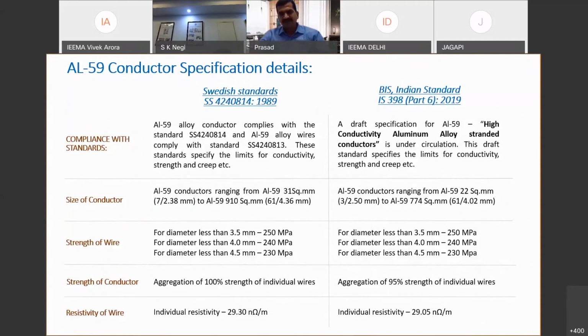But the important factor we can look at is how the overall UTS of the conductors is calculated. The Swedish standard allows 100% strength of the individual wires, which can be aggregated to arrive at the breaking load of the conductor, whereas in the Indian standard we have 95% of the individual strength of the wires. At the same time, in the Swedish specification, if we achieve 90% of the UTS which we have confirmed, then it is okay. Whereas the Indian standard is a refined version, and in the recent TBCB specifications, we should achieve 100% of the UTS which we are guaranteeing. So I would say that we have refined and very particular standards.